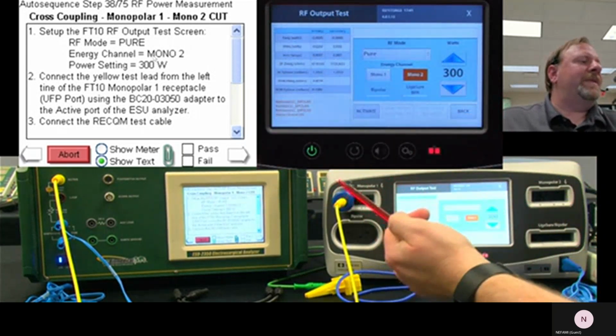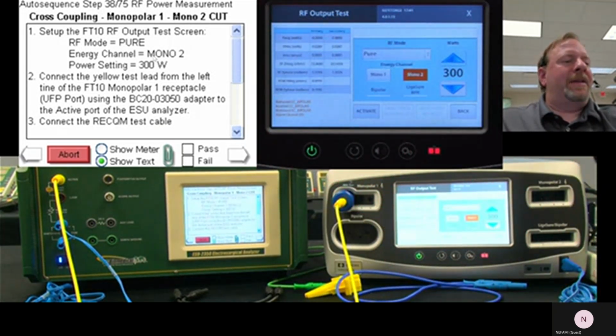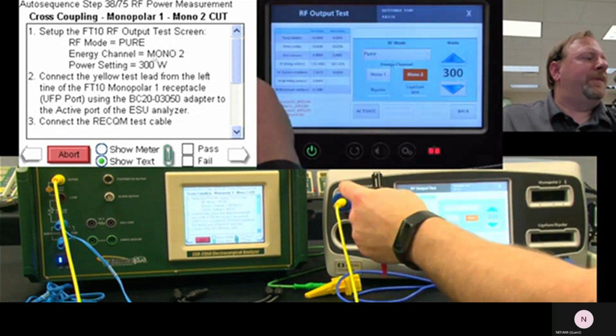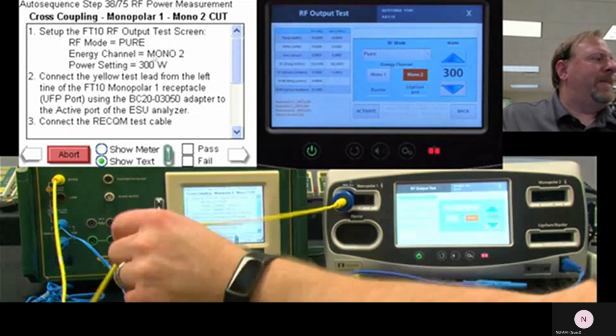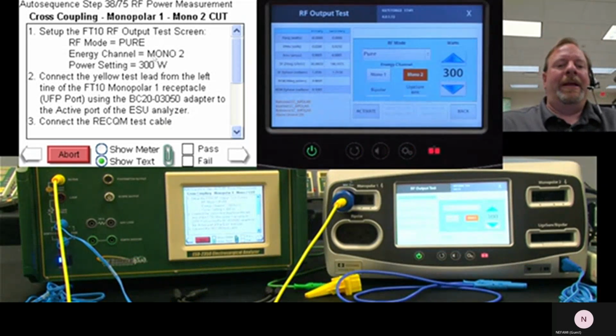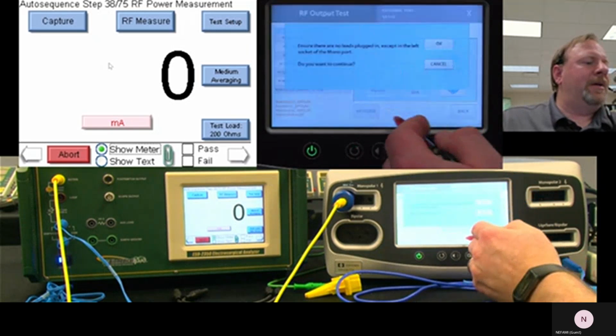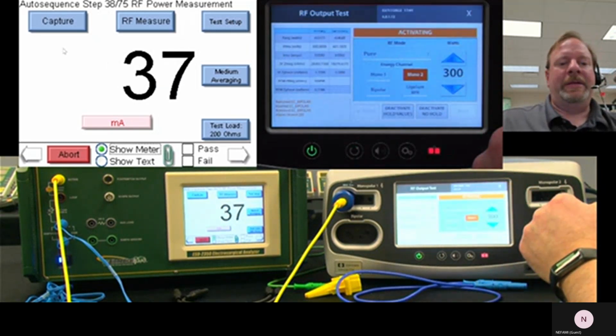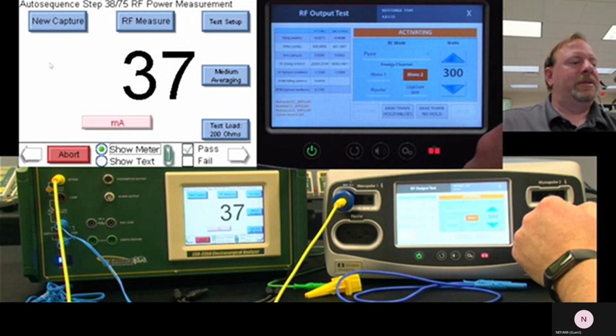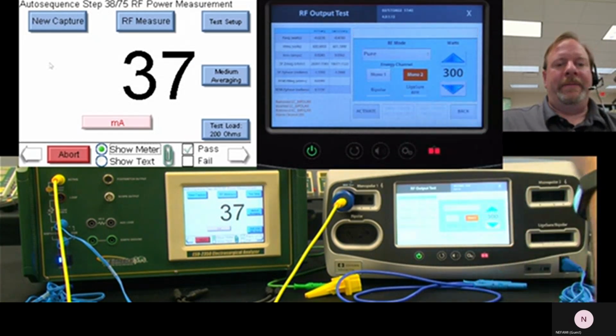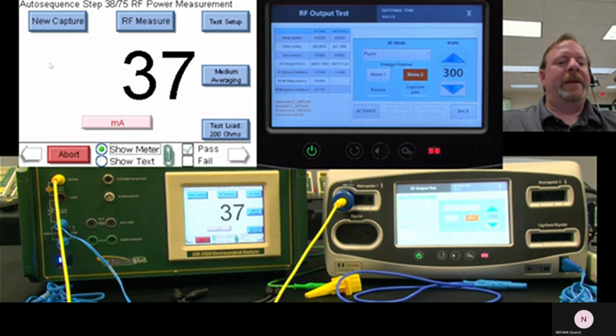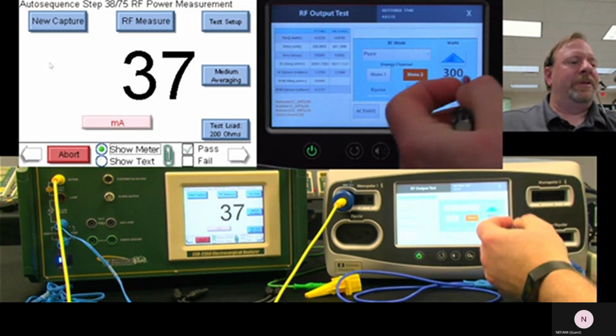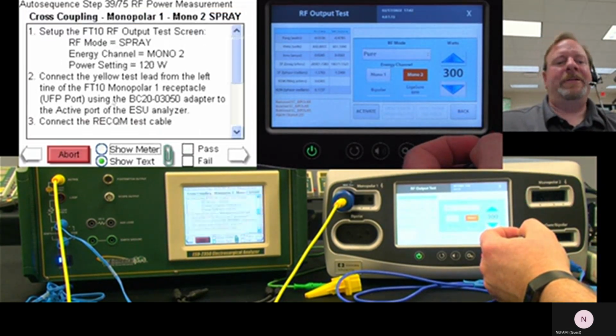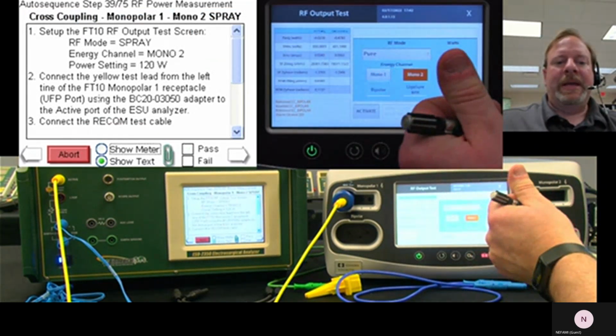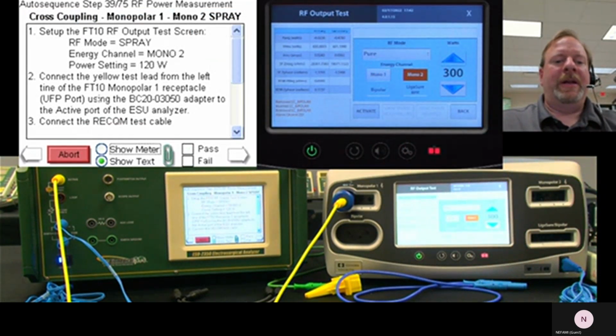So this is actually a safety issue. They're activating this output, but what happens if, how much energy could accidentally come out this port that is the unintended port? And so that's a very real concern. And so we have to test that and make sure that that is under a limit specified by Covidien. Now they've done the analysis, they've done all the testing, and so they know what this should be. So 37 is acceptable.